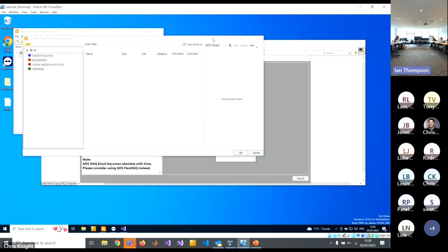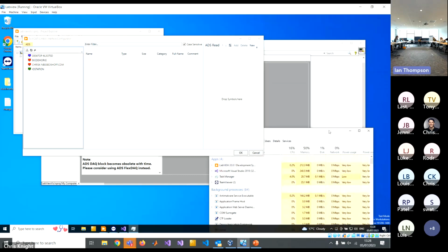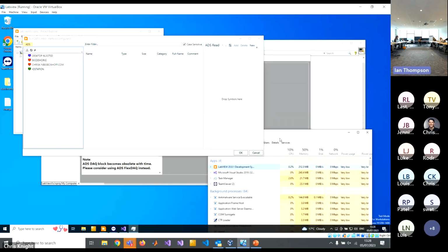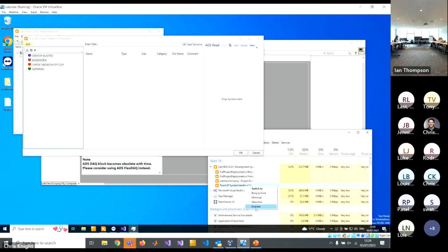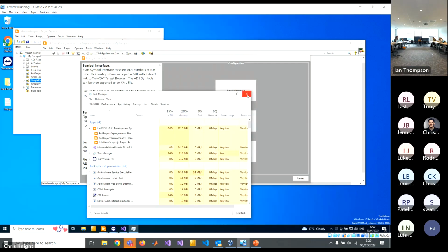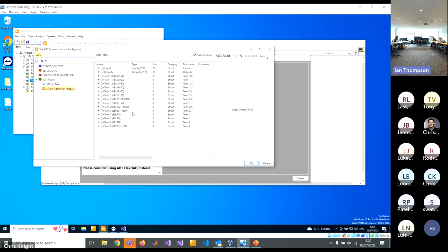Chris, that creation of that task in that last bit you ran is the bit that enables you then to access it via that library that you guys have developed. Is that right? Yeah, the automation interface allows me to basically parameterize an entire TwinCAT system. It allows me to create the image, scan in the IO, and add in a task that then lets me run the IO.